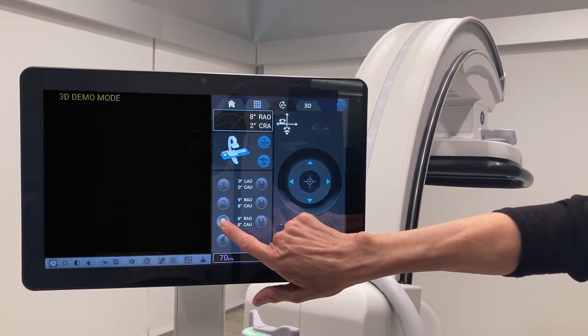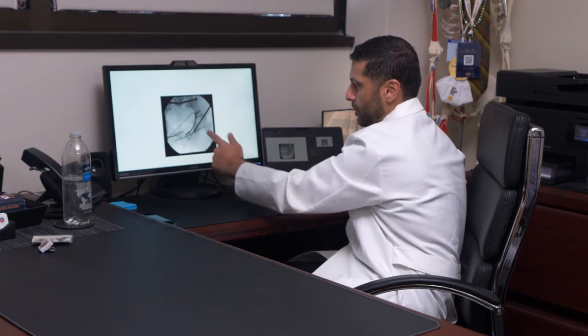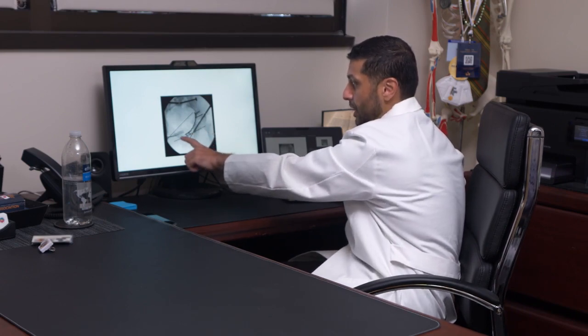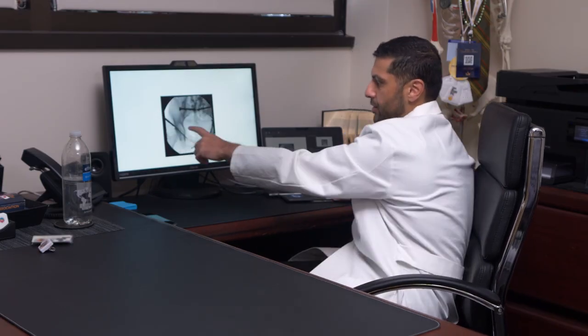To be able to zoom in on the image without magnifying also is a feature that we've used some, but probably should use more even, to help lower our radiation exposure to patients. In addition, we can do the post-processing reduction of metal artifacts. We can do it on the front end before we even run the scan, and therefore it's just a one-time process and easy for us to use. And again, this is all within a few minutes right there live in the operating room, so we can make changes if we need to.